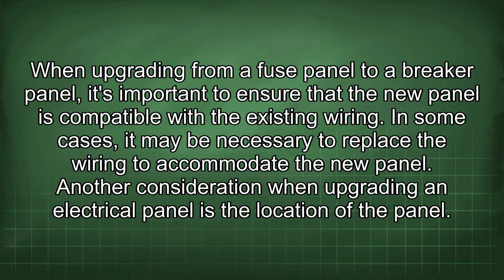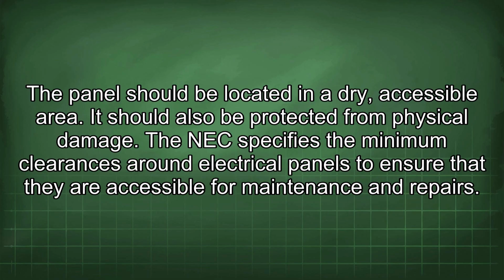When upgrading from a fuse panel to a breaker panel, it's important to ensure that the new panel is compatible with the existing wiring. In some cases, it may be necessary to replace the wiring to accommodate the new panel. Another consideration when upgrading an electrical panel is the location of the panel. The panel should be located in a dry, accessible area. It should also be protected from physical damage. The NEC specifies the minimum clearances around electrical panels to ensure that they are accessible for maintenance and repairs.